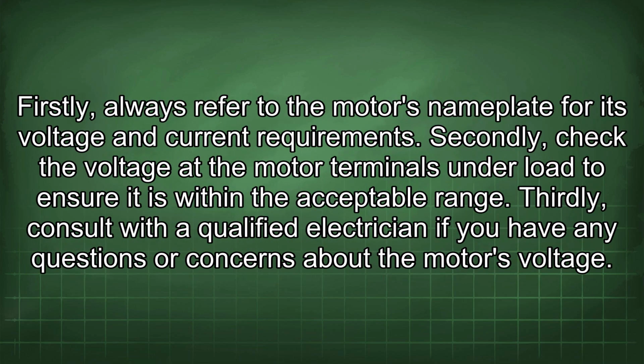Firstly, always refer to the motor's nameplate for its voltage and current requirements. Secondly, check the voltage of the motor terminals under load to ensure it is within the acceptable range. Thirdly, consult with a qualified electrician if you have any questions or concerns about the motor's voltage.